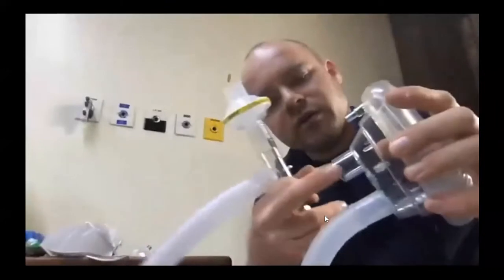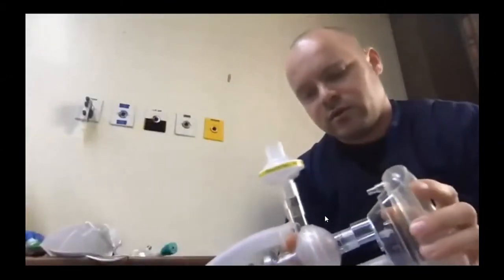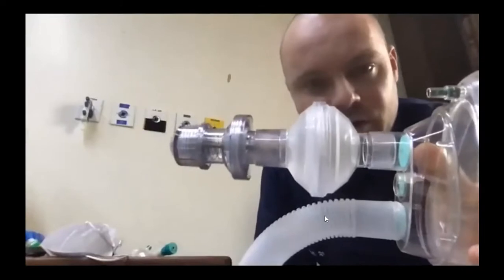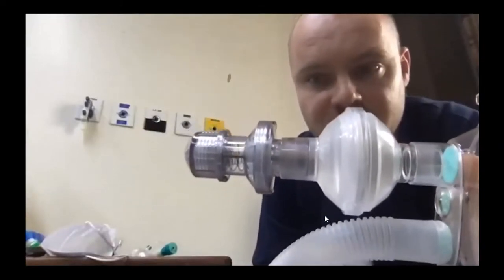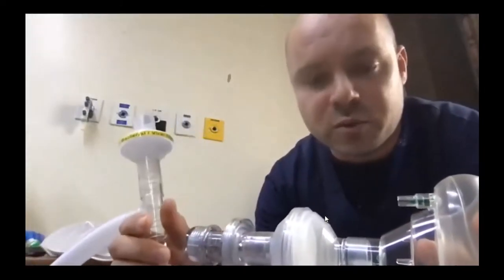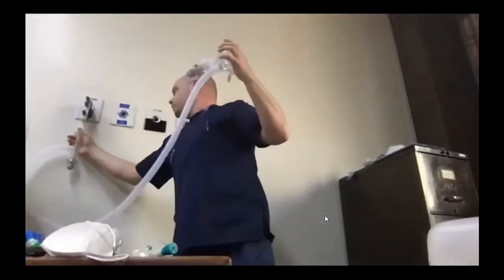And then on the outlet port here, we're going to have, again, a viral filter so that we're not contaminating the environment, and the PEEP valve that we're going to use to select therapy. So once you're connected, the most important thing is potentially going to be to make sure that you've actually got a decent patient seal before you even initiate flow, because we've got both an anti-asphyxia valve on this mask, and the device itself acts as an anti-asphyxia valve. You can apply it with zero flow and make sure that you've got a good patient seal.